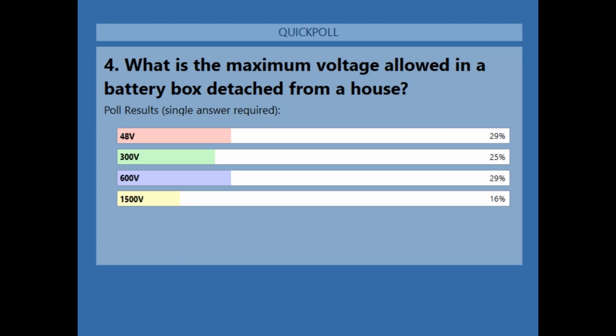And so you might find yourself designing an off-grid cabin where the array is really far away from the site, and you think, well, can I treat my ground mount like a utility scale array and run high voltage lines? The answer is yes. There are some additional constraints, mainly to do with site security. You'll need to fence off the solar array so no one can get into it. But if you're already building a secure battery box and you put a lockable fence around your solar array, you can do a 1,500 volt design if you want to, even though it's a residential property, as long as the array is detached from the house. So if you're detached from the house, you can be over 600 volts. If you're attached to the house, you have to be 600 volts or lower.